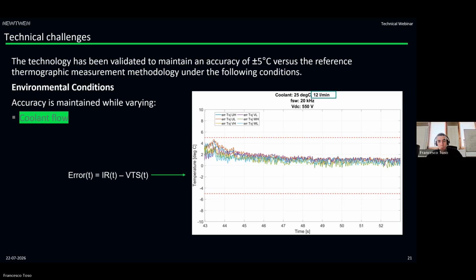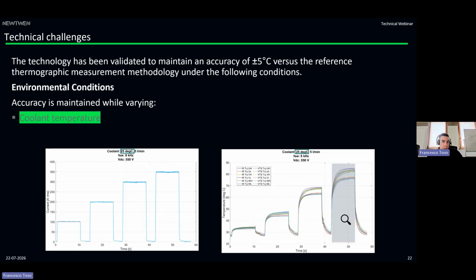Coolant flow for sure was one of the challenges, but also the coolant temperature can change, because if we think about the chiller in a cooling system, not always it operates with the nominal temperature of the coolant. And sometimes, not in all the systems that we operate within, the coolant temperature is a known variable. So sometimes you don't have information on the temperature of the inlet of the coolant.